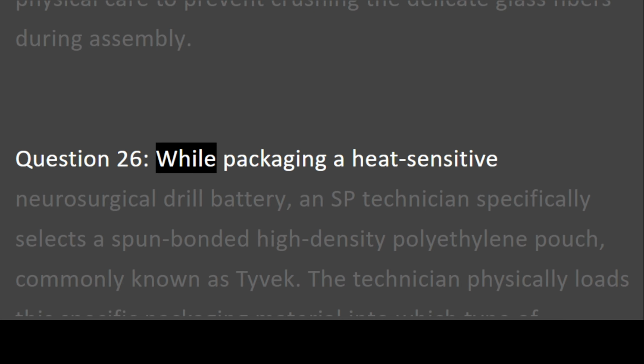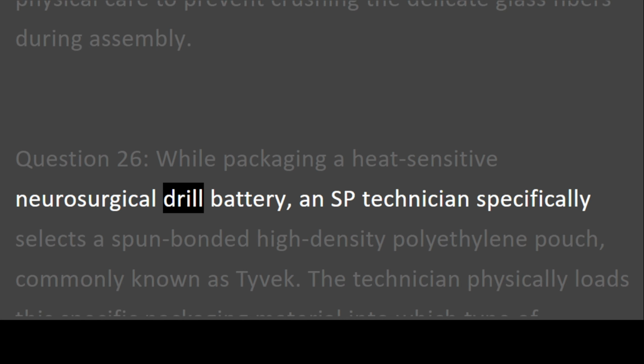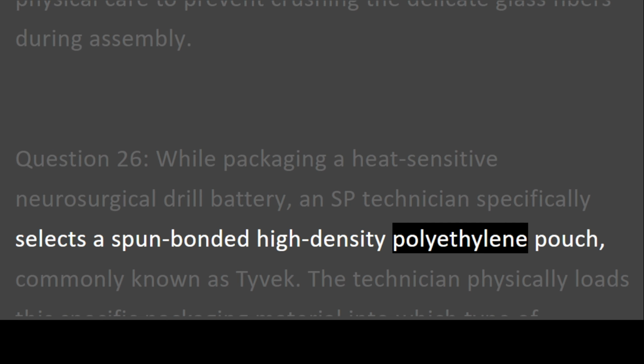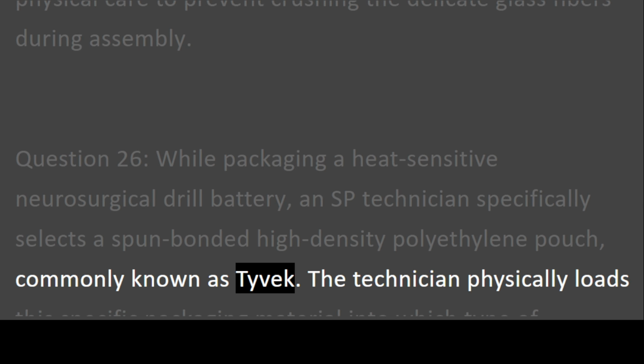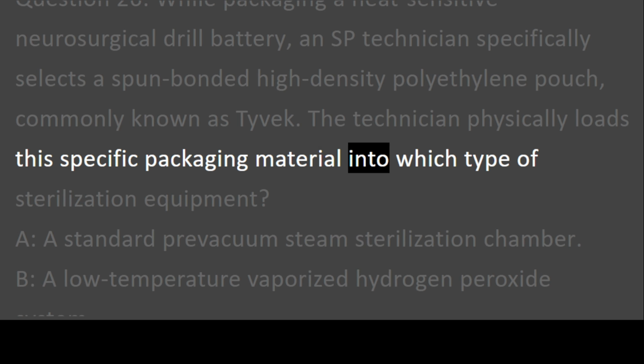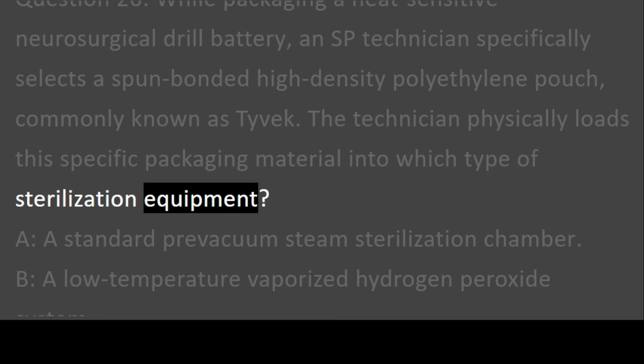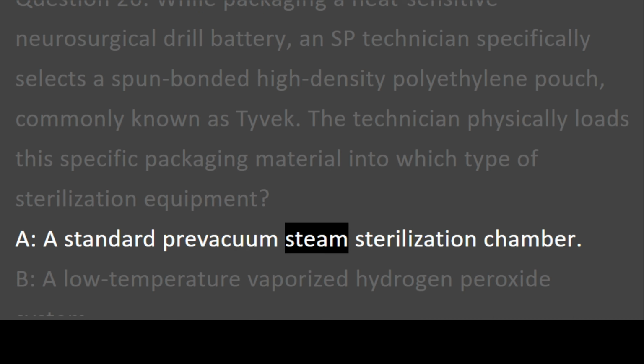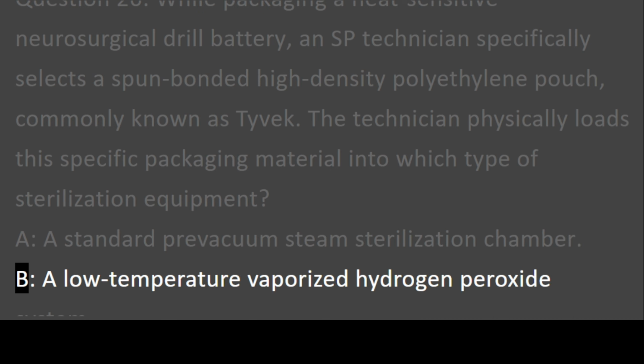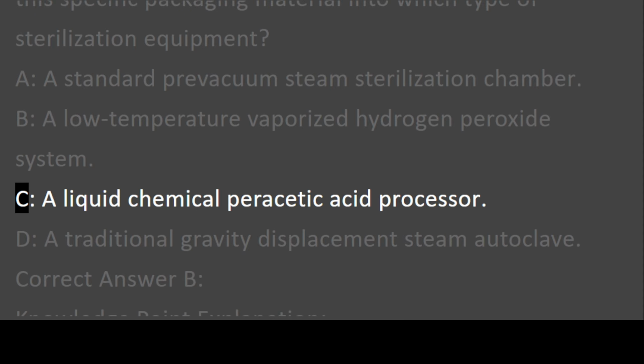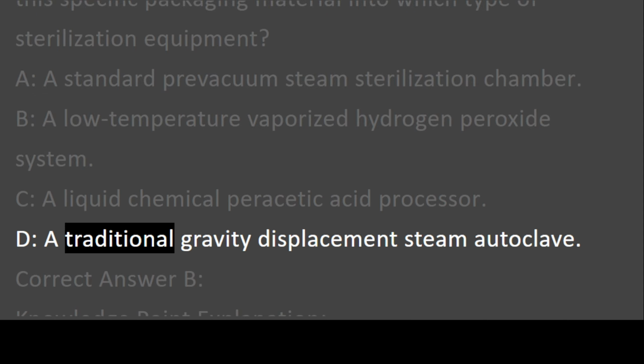Question 26. While packaging a heat-sensitive neurosurgical drill battery, an SP technician specifically selects a spun-bonded high-density polyethylene pouch, commonly known as Tyvek. The technician physically loads this specific packaging material into which type of sterilization equipment? A. A standard pre-vacuum steam sterilization chamber. B. A low-temperature vaporized hydrogen peroxide system. C. A liquid chemical peracetic acid processor. D. A traditional gravity displacement steam autoclave.